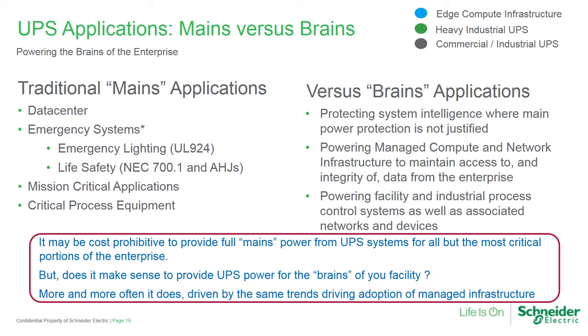This is dictated by code, which is interesting in that outside of emergency lighting, which it clearly states as an emergency system, it more tells you how to handle emergency systems rather than defining what they are. When you get into mission critical IT applications and critical process equipment, determining what equipment is critical to your process is part of a risk analysis done between you, your authority having jurisdiction, and your process experts, to decide which systems require full power backup to maintain highest availability, versus those where you can simply protect the system intelligence and network. That's what we call the brains.